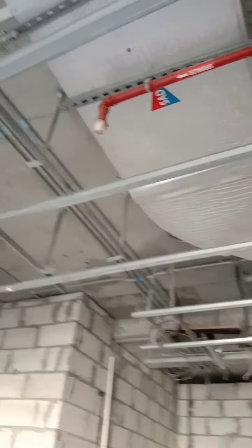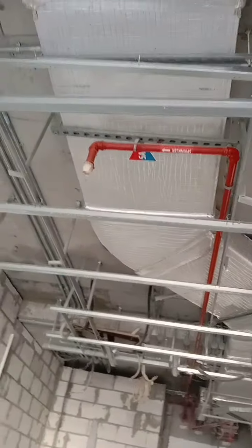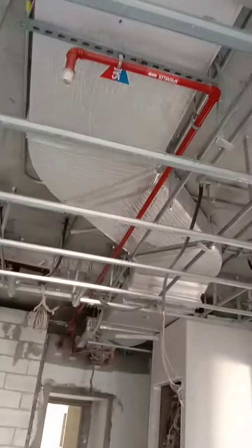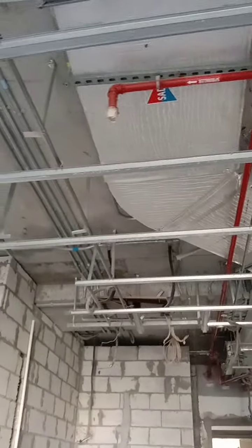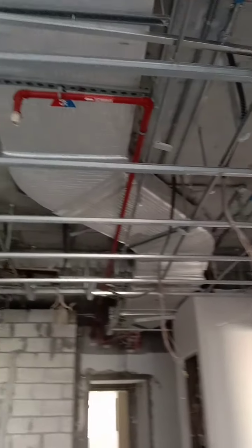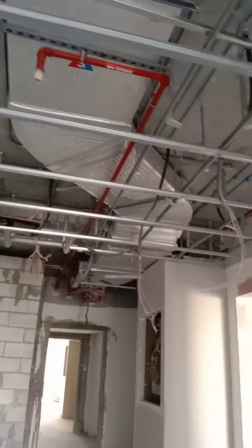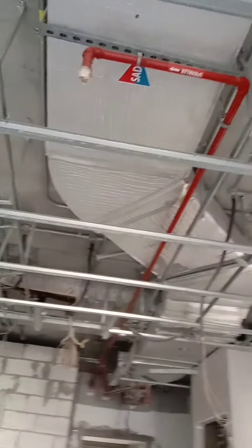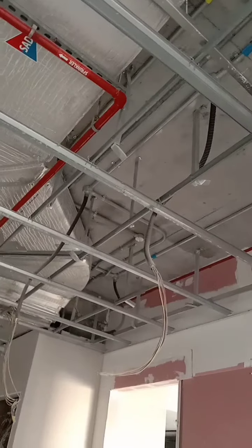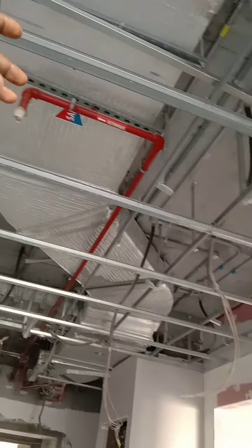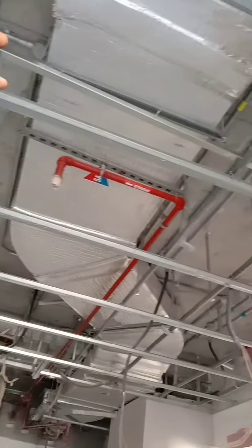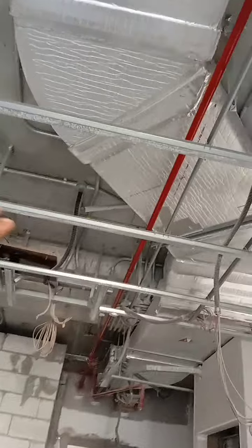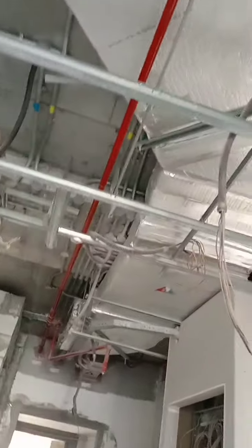For small power systems, we have to ensure that all the different services to be installed above the false ceiling are completed before we sign off or give clearance for that particular location. For fire alarm systems also, we have to ensure whether we have smoke detectors, but in this location we don't have any smoke detectors, because the height from the soffit to the false ceiling is not that much, so we don't require any smoke detector at the false ceiling level.